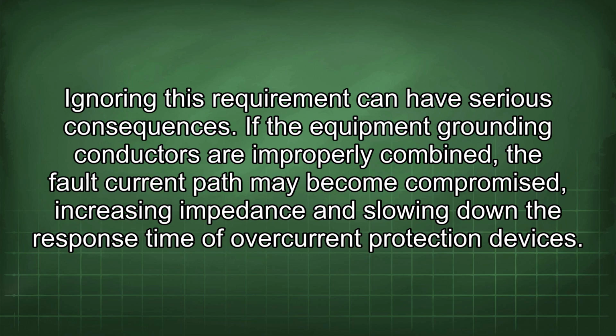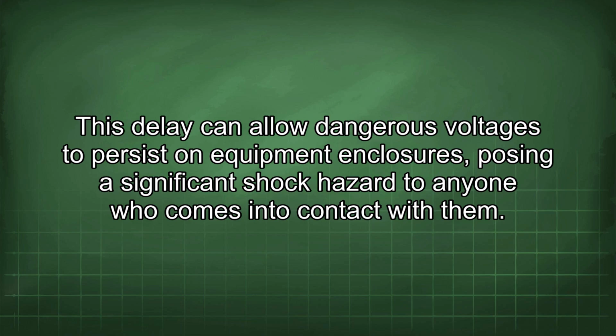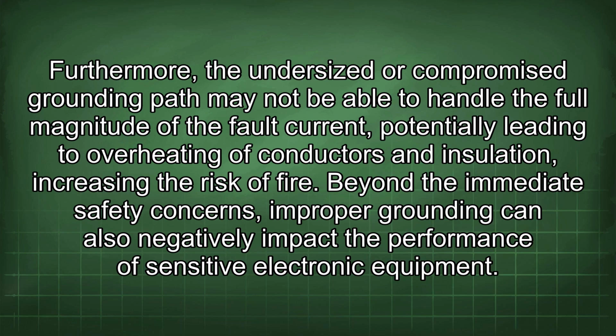If the equipment grounding conductors are improperly combined, the fault current path may become compromised, increasing impedance and slowing down the response time of overcurrent protection devices. This delay can allow dangerous voltages to persist on equipment enclosures, posing a significant shock hazard to anyone who comes into contact with them. Furthermore, the undersized or compromised grounding path may not be able to handle the full magnitude of the fault current, potentially leading to overheating of conductors and insulation, increasing the risk of fire.